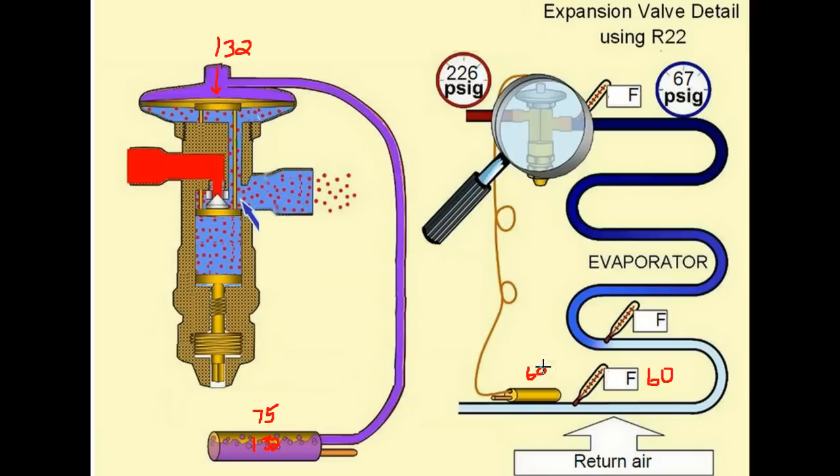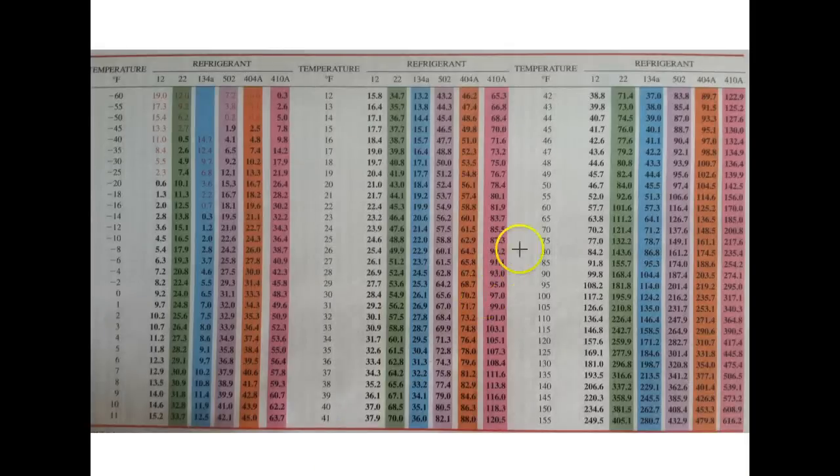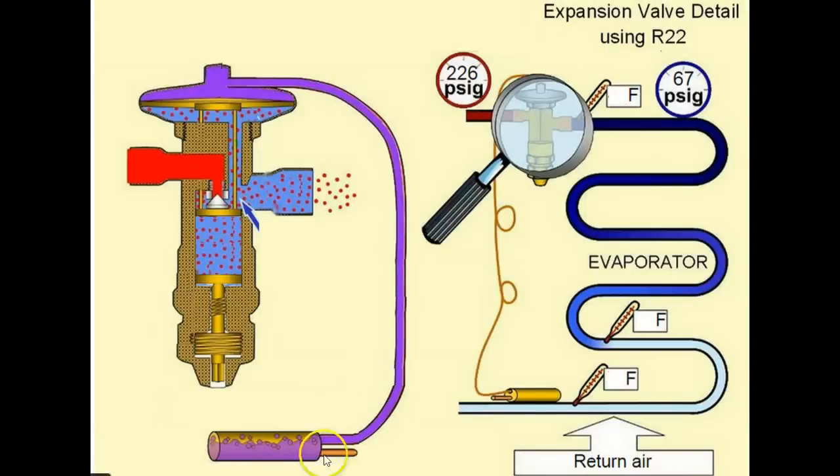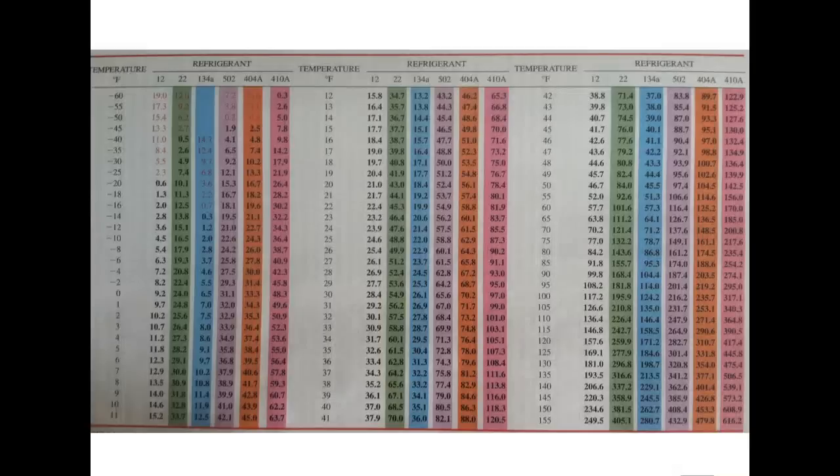And the sensing bulb is 60 degrees. And if we take a look at what 60 degrees pressure is, the relationship, the PT relationship. Let's look at 60. Now it's 102 PSIG.